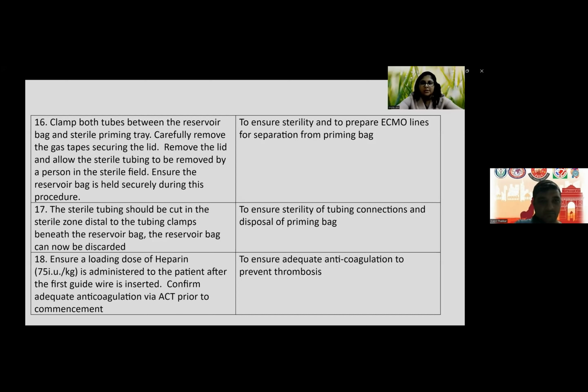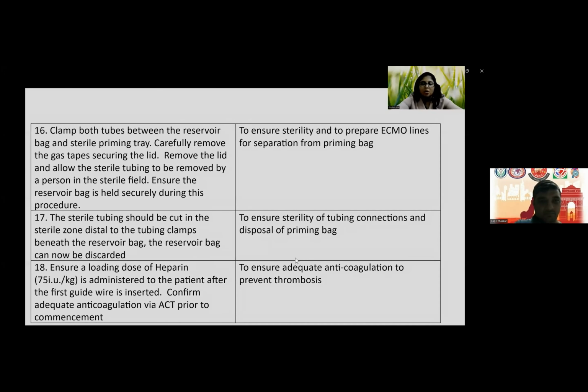This is to ensure the sterility and prepare the ECMO lines for separating from the priming bag. Then the sterile tubing should be cut in the sterile zone, distal to the tubing clamps beneath the reservoir bag, and the reservoir bag can be discarded. So this is to ensure sterility of the tubing connections and disposal of the priming bag.